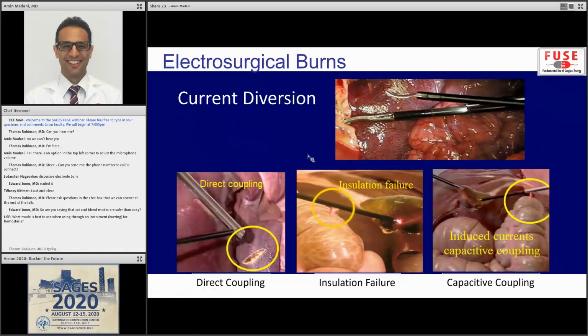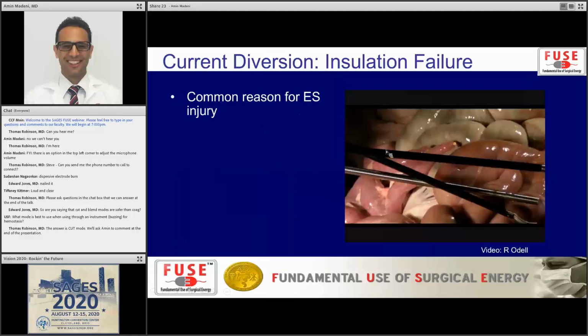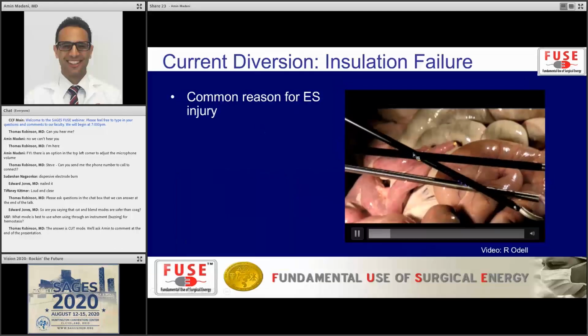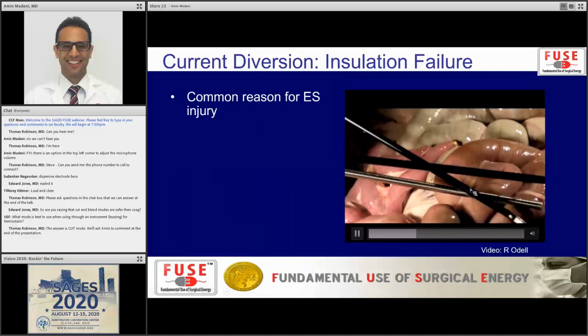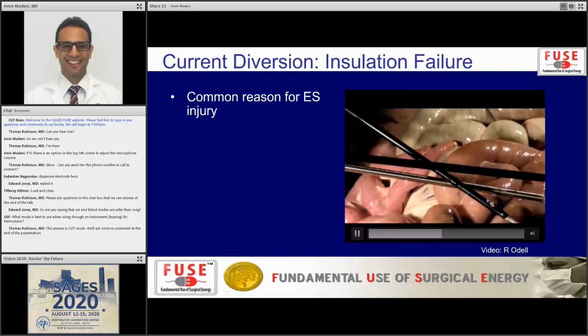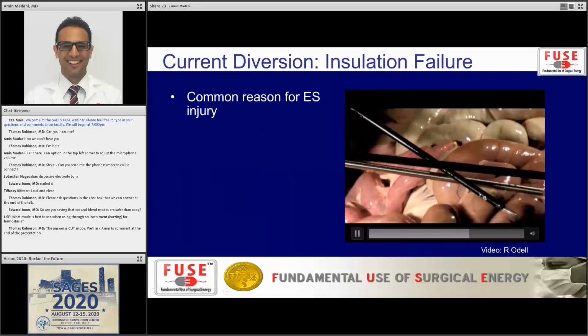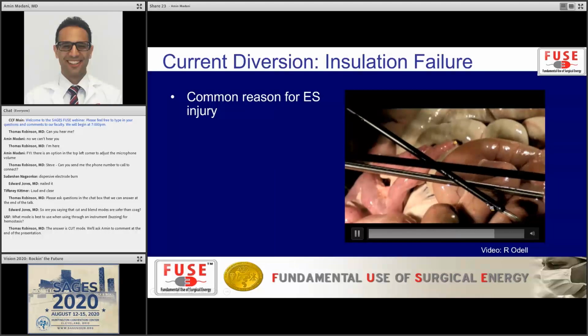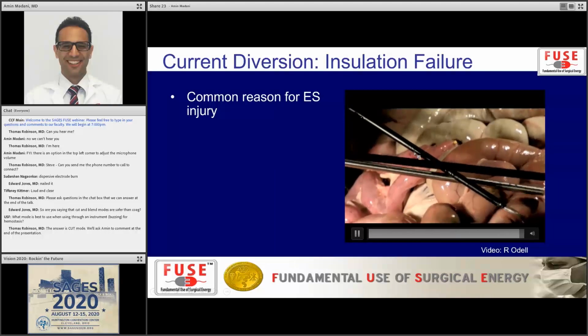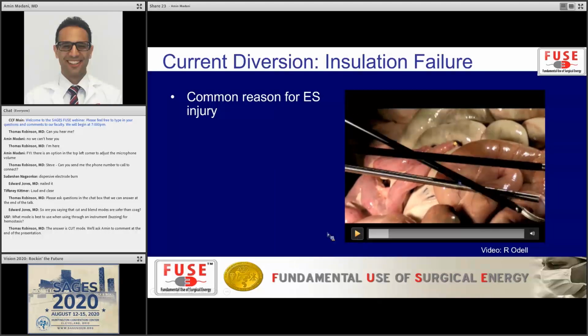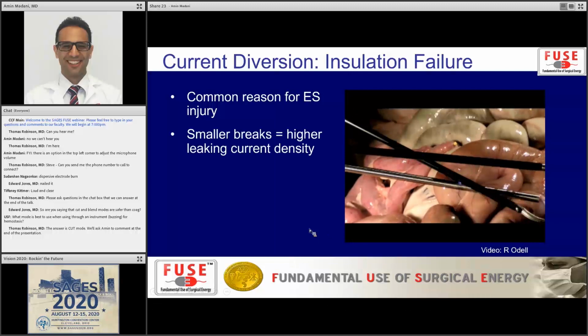The other major problem that can happen is something called current diversion. Current diversion just means your current does not go through the path that you want it to go, and there's a variety of ways this can happen. One of them is through something called insulation failure. Let's say you have breaks in the insulation, completely outside your field of view, and you can be touching other instruments that can divert current. That's one way current diversion injuries can happen.